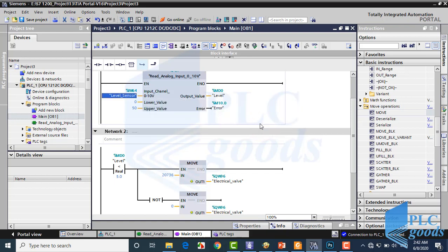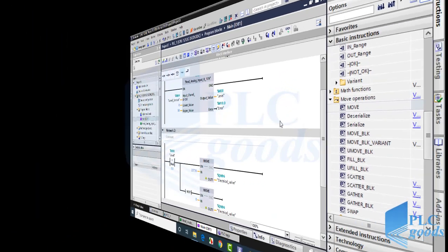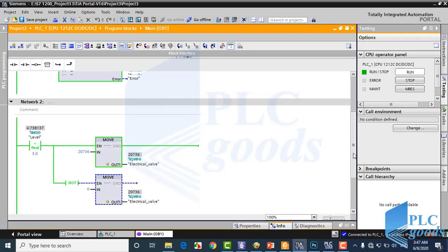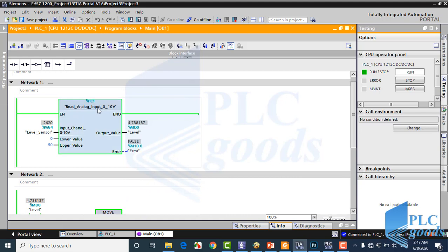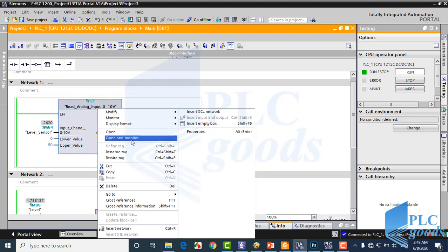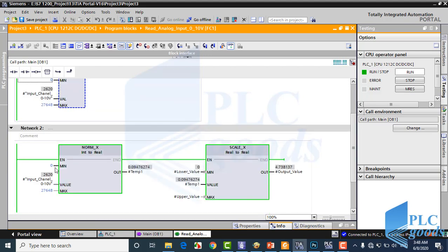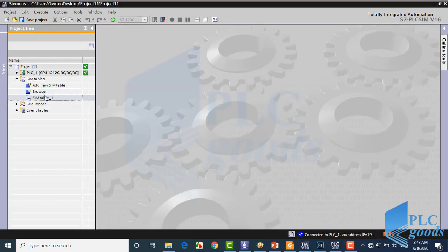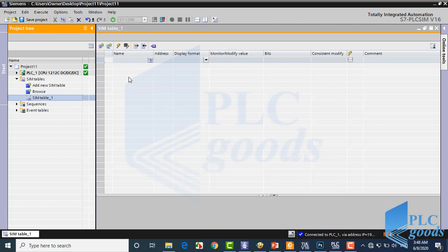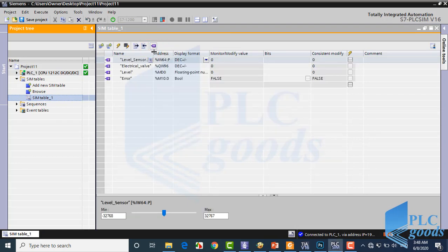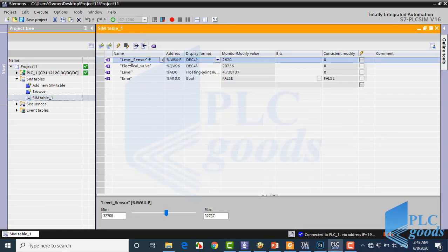Let's test this program with SimTable. This is my program, and this is my function. Pay attention to insert the min and max values correctly. Let's test the program with SimTable. These are the tags used in my program: level sensor, electrical valve, level, and error.